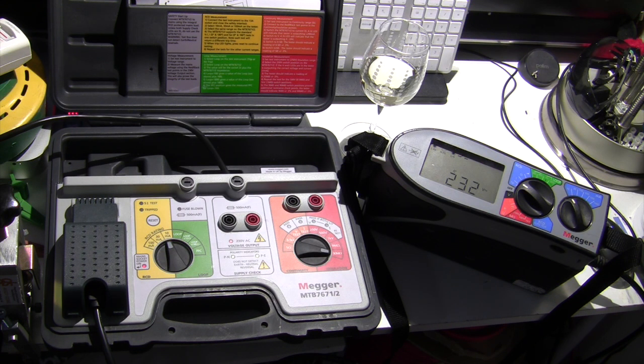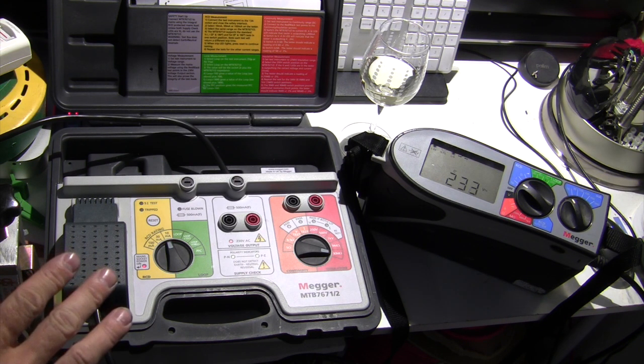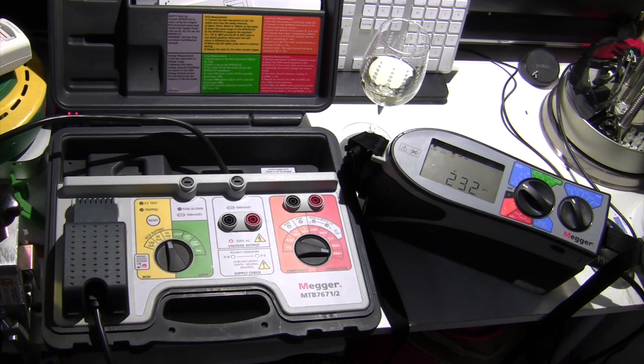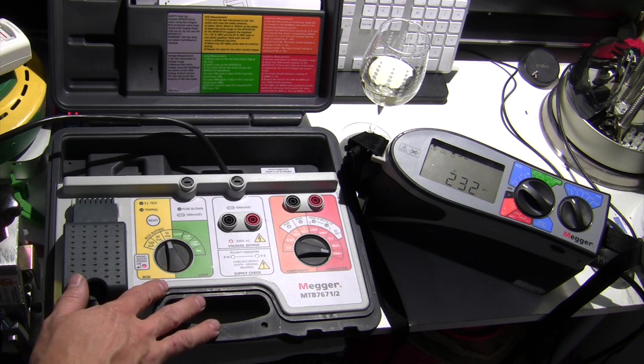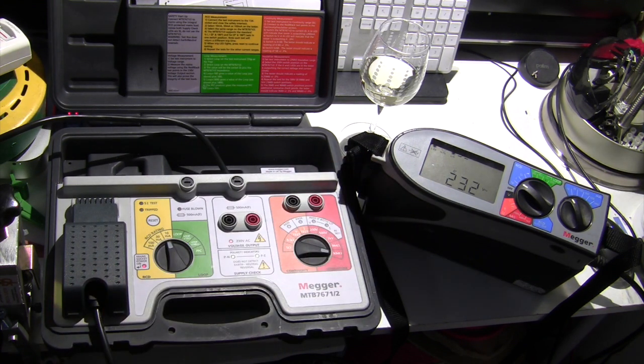If it's an older RCD to BS4293, then those numbers are 200 milliseconds and 40 milliseconds. This is different because this is a simulation, remember, so we're not expecting the same kind of results, and what we are expecting here is a reaction within 40 milliseconds. So instead of the usual 300 milliseconds of leeway, we've got 40 milliseconds of leeway at 0 degrees. So we should see a number below 40 milliseconds.